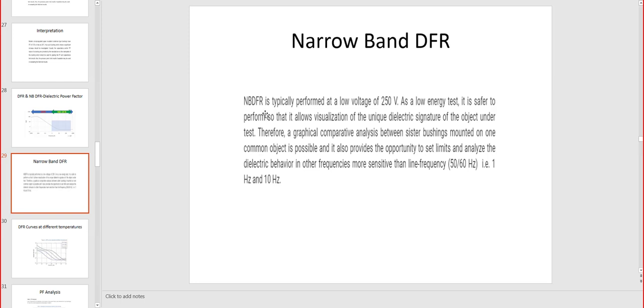Narrow band is typically performed at low voltage, so for narrow band we typically apply 250 as a low energy test. It is safer to perform. It allows visualization of the unique dielectric signature of the object tested. Therefore, graphical comparative analysis between sister bushings mounted on one common object is possible. So you need to be familiar. When you have a new transformer, you need to do this test and have a base, so that will be used as a starting point.